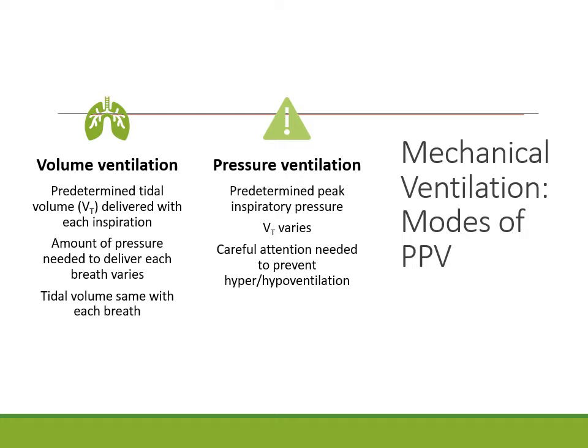With volume ventilation, a predetermined tidal volume is delivered with each inspiration, and the amount of pressure needed to deliver the breath varies based on the compliance and resistance factors of the patient ventilator system. Consequently, the tidal volume is consistent from breath to breath, but the airway pressure will vary. With pressure ventilation, the peak inspiratory pressure is predetermined. The tidal volume delivered to the patient varies based on the selected pressure and the compliance of the patient ventilator system. Careful attention must be given to the tidal volume to prevent unplanned hyperventilation or hypoventilation.